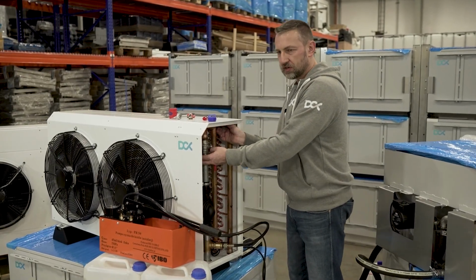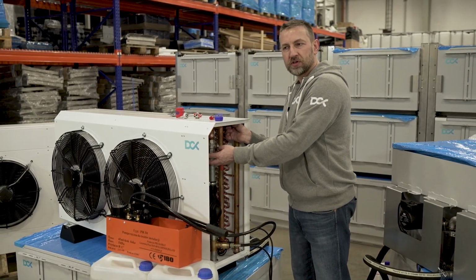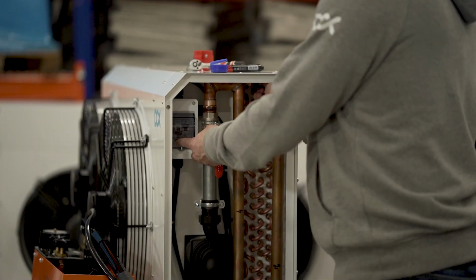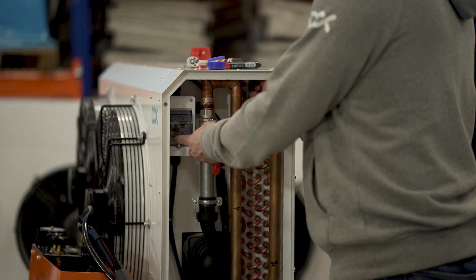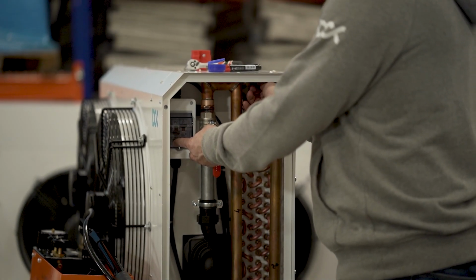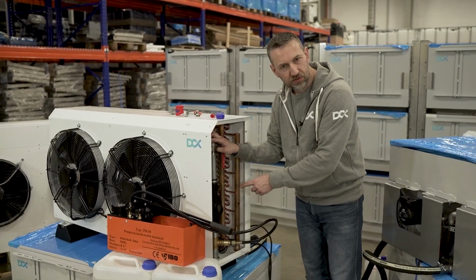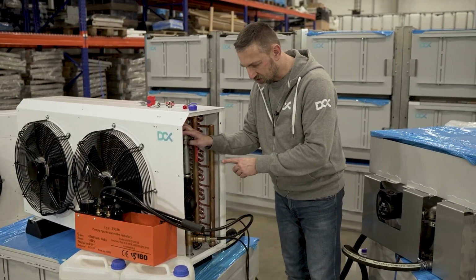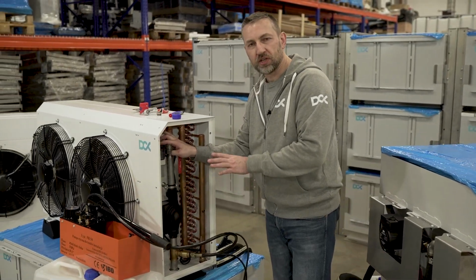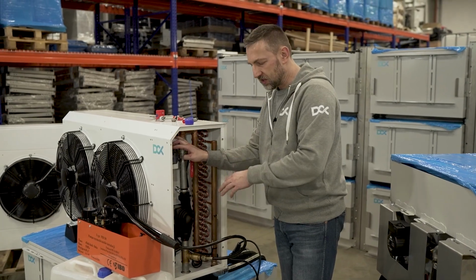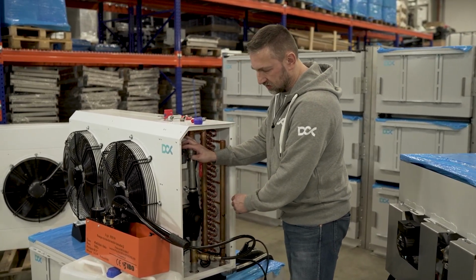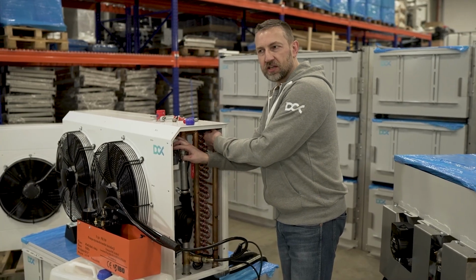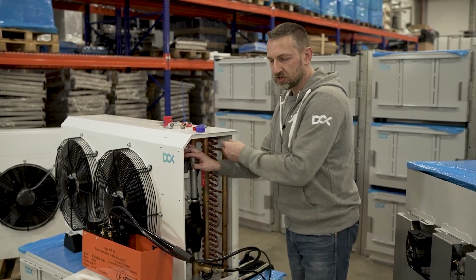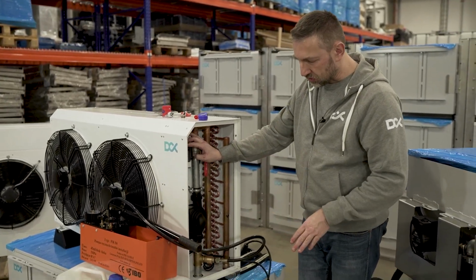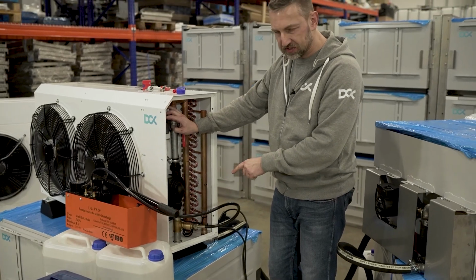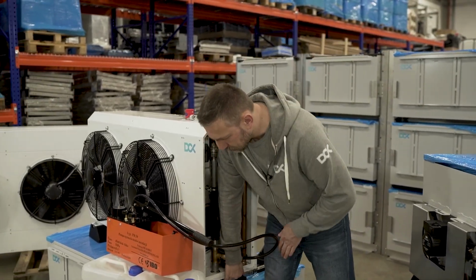And if I use that air vent again, or open that air vent a little bit more, I just save some air here to show you. Again, you'll be able to hear the air leaving the system, right? And if you hear an uneven sound of the pump, then it means that you need to take some time, depressurize, add some pressure, and wait for the air to gather here, and then open that additionally, release some air, or wait a little bit. What also helps is if you lift that unit a little bit, so just shake it a little bit.